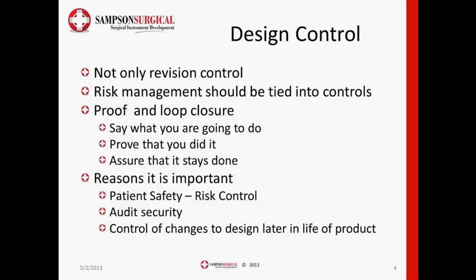Just a brief discussion about why it's important. These are just 3 reasons, and of course there are more. Initially, patient safety or risk control is a big aspect of this requirement, and we don't want to assume that something identified in the design control as important to patient safety was correctly addressed. We want to assure that that's done. We also want to quickly identify what was done in an artifact in an audit, what caused that artifact or where it came from, and what the progression was after it, so that we can quickly get to the data that we need as part of an audit.